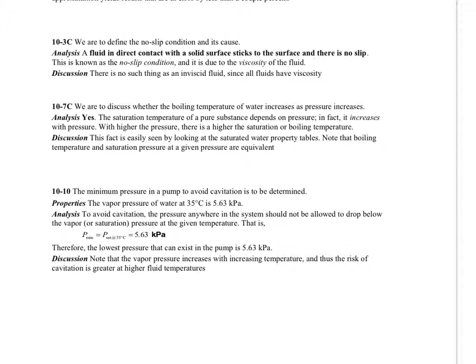Now let's look at question number 10. You're supposed to consider the minimum pressure in a pump to avoid cavitation. So if you look at tables at 35 degrees, you will generally see that the saturation pressure is 5.63 kilopascal. What does it mean? It means that at 35 degrees centigrade, if the pressure drops to 5.63 kilopascals or 0.0563 bar, you will have the condition when the water will change from liquid to gas. And remember, when we talk about the gaseous state of water, we refer to it as steam.